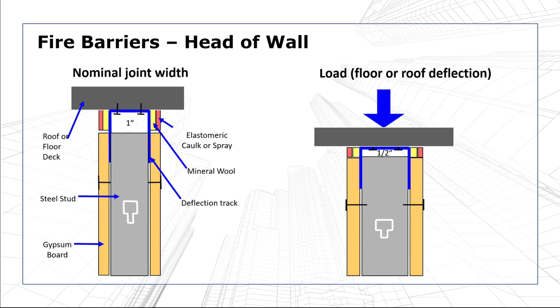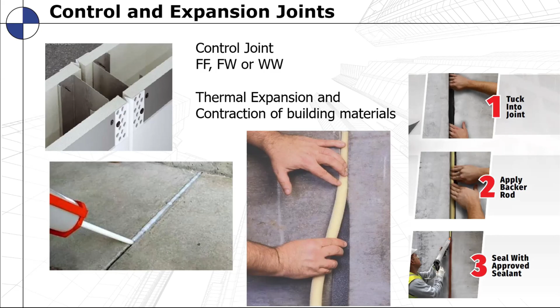that it still does its job. There are all kinds of joints in structures. Control joints and expansion joints happen throughout structures most of the time. These are either complete building separations or they're separations in building materials, and they have to be filled in with something. If they're fire rated, they have to be filled in with some type of fire rated material, which would be either a Firestop sealant or it would be filled in with a Firestop pre-cured material, like in this case, a joint strip material, which is a wrap type style material that we looked at earlier. Those instances were around a pipe. This is actually being installed in a linear joint with a backer rod and then Firestop sealant.